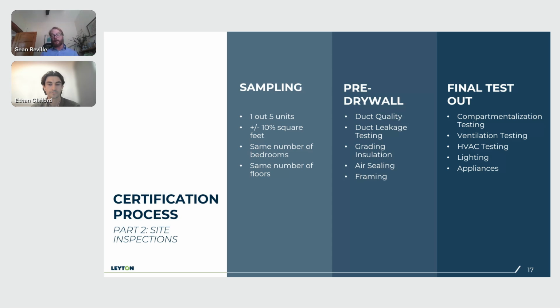So there's 2 required inspections, though you can opt to do more. There's 2 that are required no matter what, which is the pre-drywall and the final test out. At the pre-drywall, we're looking at duct quality. So are the ducts being installed without any kinks or bends or anything that would reduce airflow? And then we're also going to do duct leakage testing, which is basically setting up a blower door fan, just a mini version, onto the duct system alone to see where air leakage is in the ducts. You don't have to do that at pre-drywall, but most people prefer to, because it gives you more access to the ducts to be able to seal them if they're too leaky or something like that.